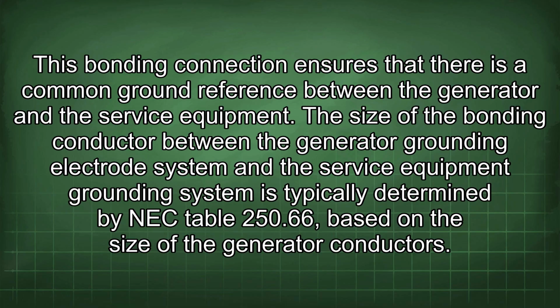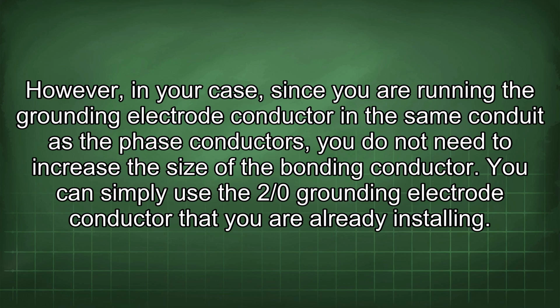The size of the bonding conductor between the generator grounding electrode system and the service equipment grounding system is typically determined by NEC Table 250.66 based on the size of the generator conductors. However, in your case, since you are running the grounding electrode conductor in the same conduit as the phase conductors, you do not need to increase the size of the bonding conductor. You can simply use the 2/0 grounding electrode conductor that you are already installing.